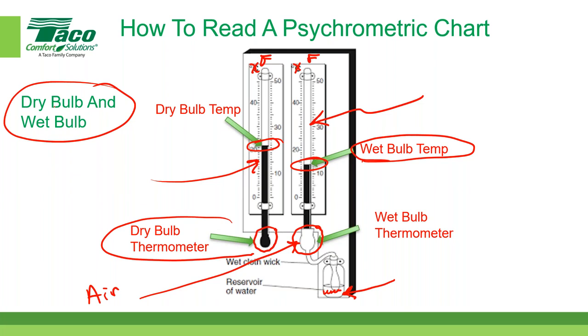And by the way, the difference between the dry bulb temperature and the wet bulb temperature is called the wet bulb depression. So I'm just going to make up a number, not the ones that are shown in this chart here. So if I had a dry bulb temperature of 70 degrees Fahrenheit, and then I had a 50 degrees Fahrenheit wet bulb measured at the same moment in time. Whoops, that's supposed to be wet bulb.